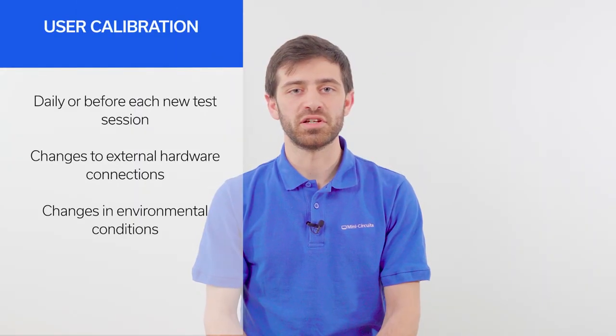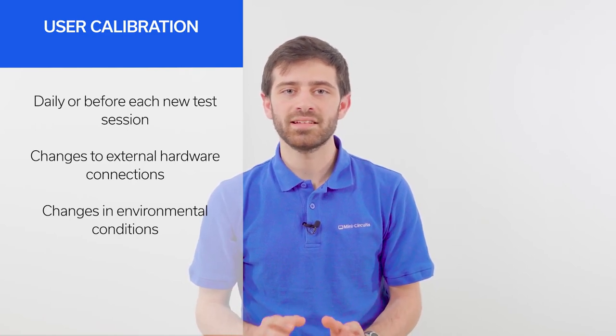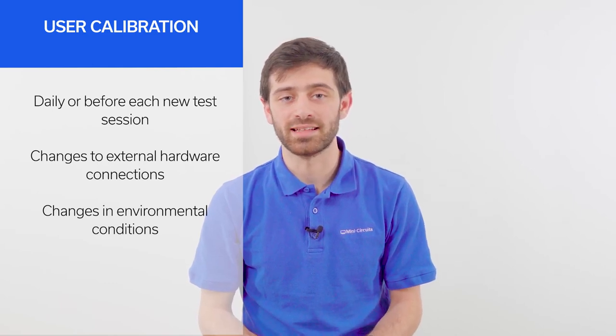You should perform a calibration first thing each day or at the start of a new test session. Anytime there's a change in the external connections of your setup or a change in the environmental conditions like temperature, it's a good idea to redo a user calibration.